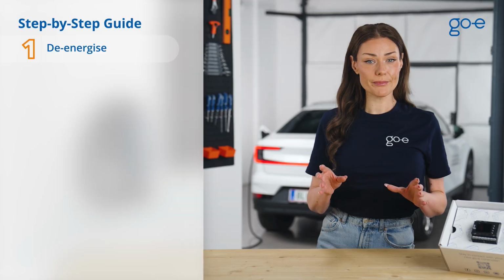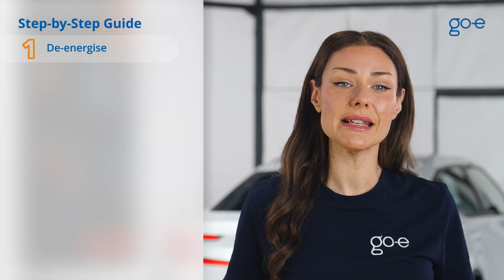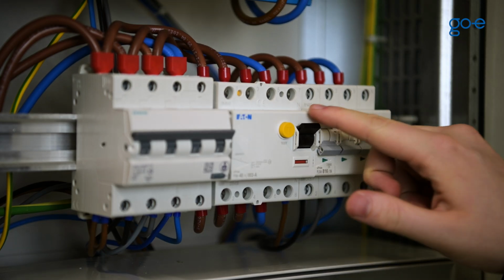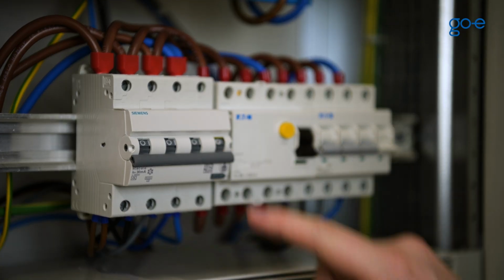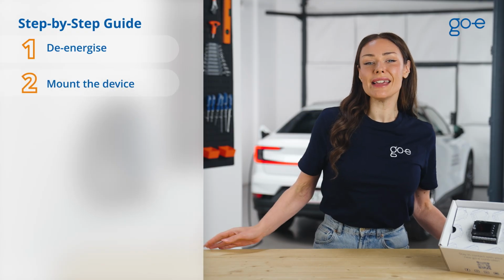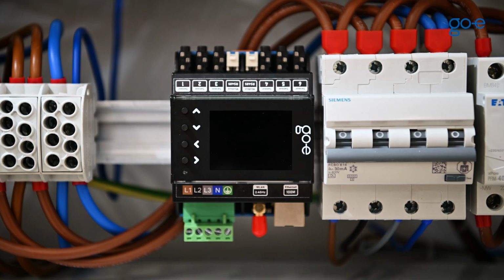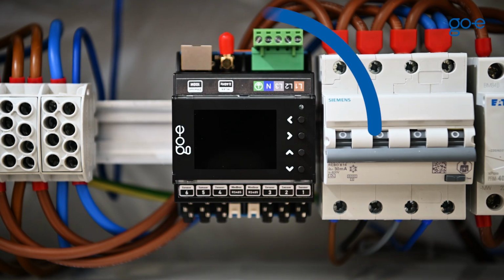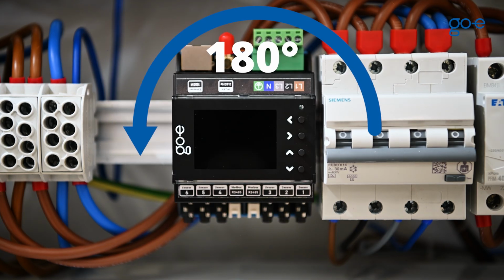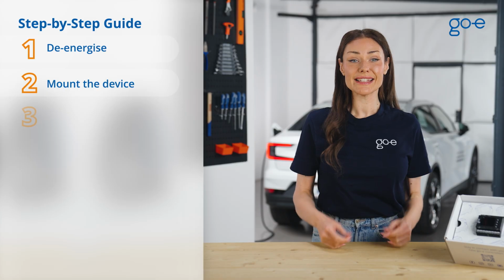So, step 1, make sure that the system is completely voltage-free according to the 5 electrical safety rules. Step 2, mount the GoE controller on the DIN rail. It can be installed either in the standard position or rotated 180 degrees depending on your preference. Rotating the device isn't a problem, since the display orientation can be changed later via the menu under Settings, Device, and Flip Display.